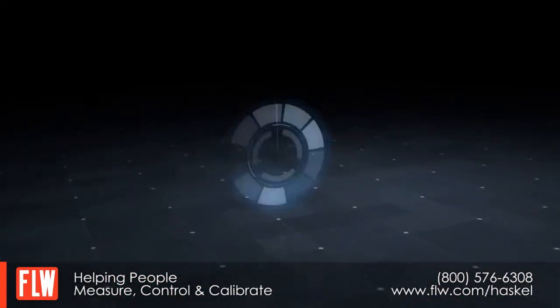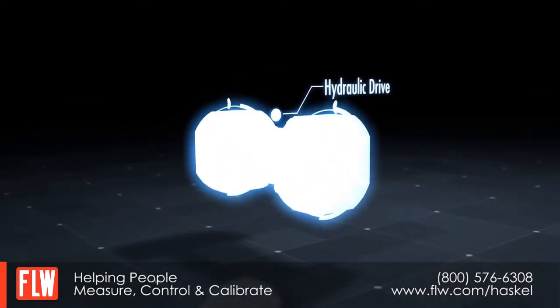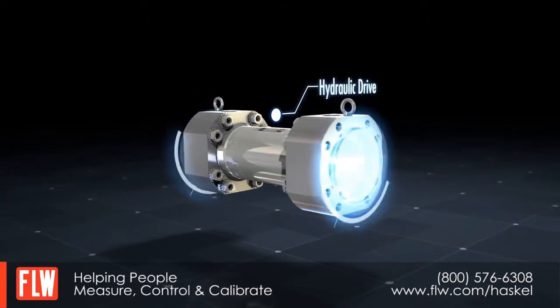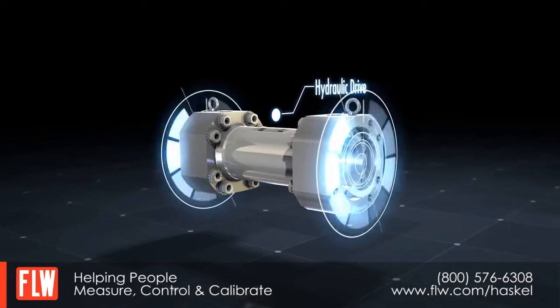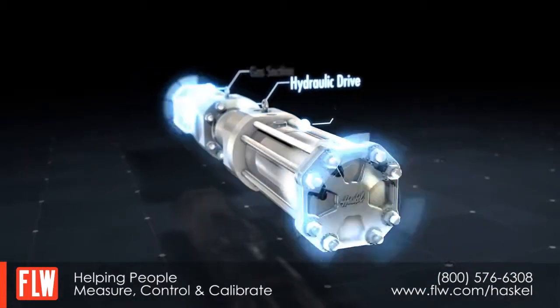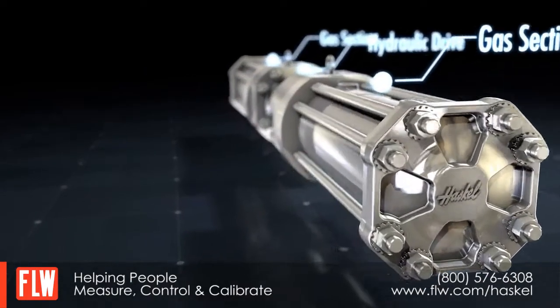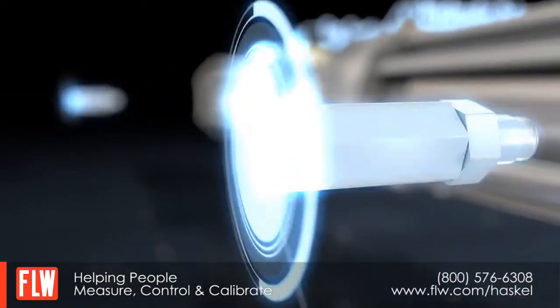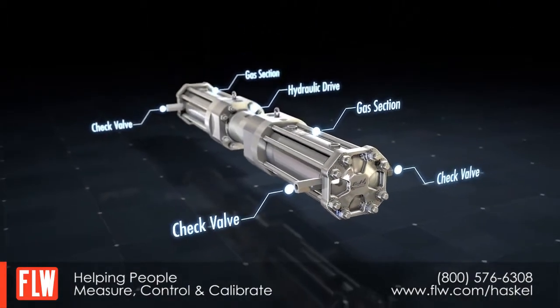Constructed of hydrogen compatible materials to resist hydrogen embrittlement, the HDRIVE booster is designed to operate at higher pressures for long range hydrogen vehicles, at approximate pressures of 700 bar or 10,000 psi. This technology enables auto vehicles to store more fuel, allowing for greater distance ranges. Models are also available to operate at nominal 400 bar or 5,800 psi for lift truck applications.